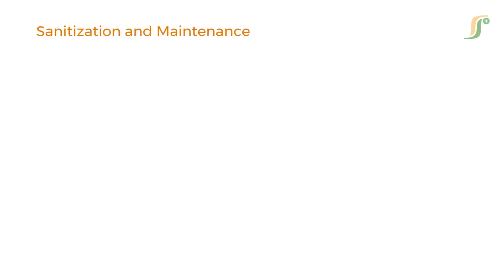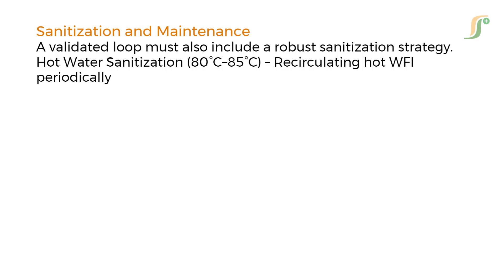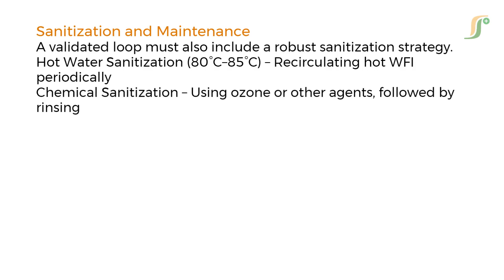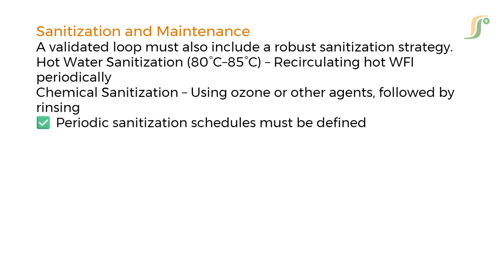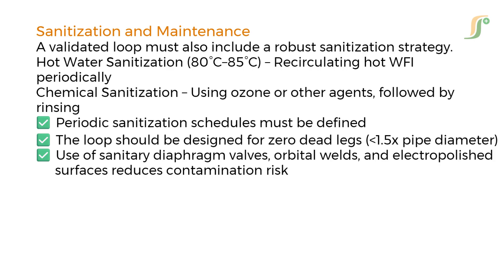A validated loop must also include a robust sanitization strategy. Common methods include hot water sanitization at 80 to 85 degrees Celsius, recirculating hot WFI periodically, and chemical sanitization using ozone or other agents, followed by rinsing. Periodic sanitization schedules must be defined. The loop should be designed for zero dead legs — less than 1.5 times the pipe diameter. Use of sanitary diaphragm valves, orbital welds, and electropolished surfaces reduces contamination risk.